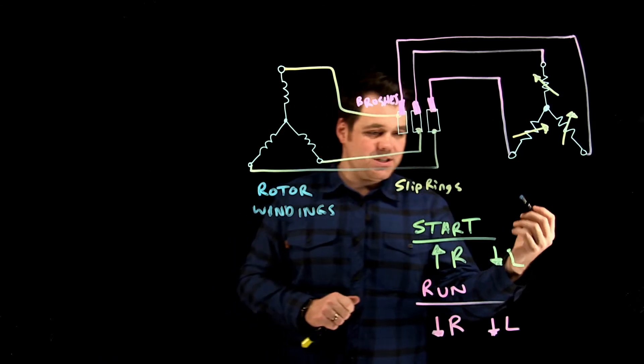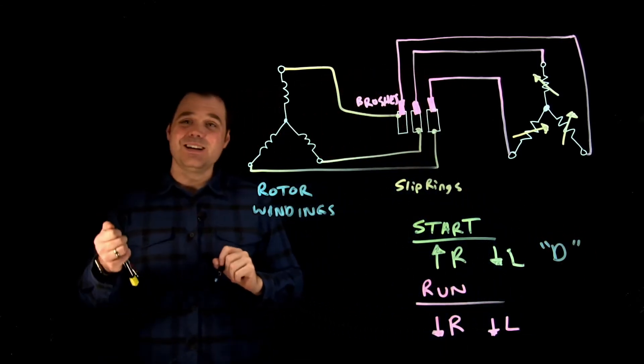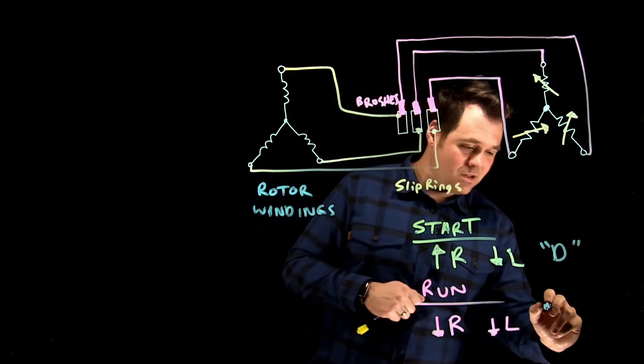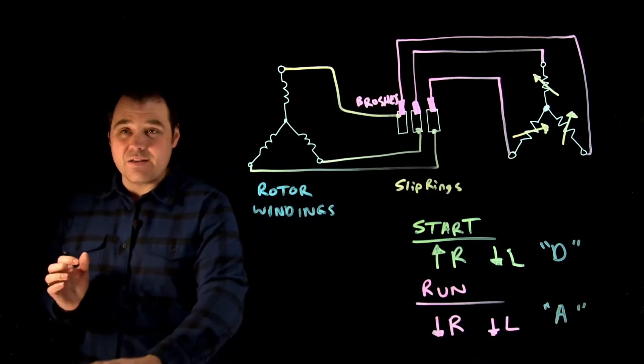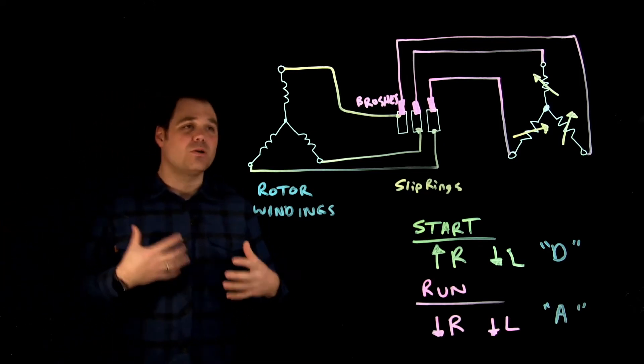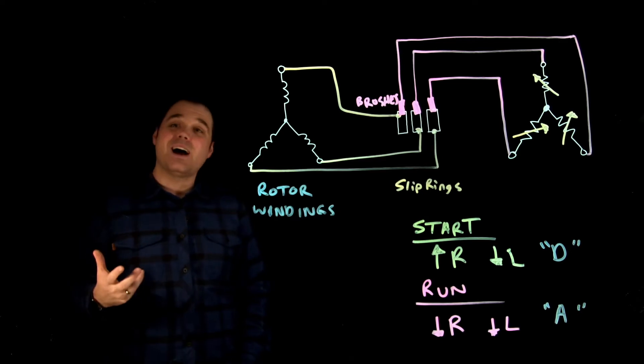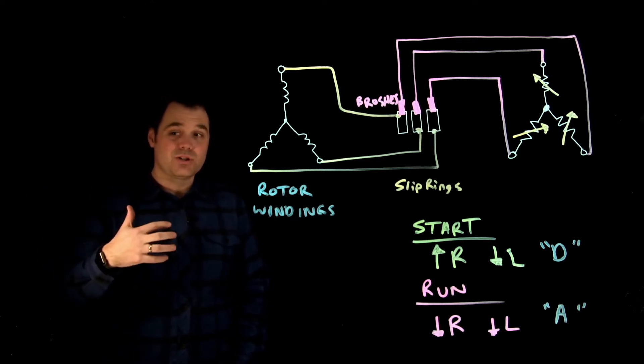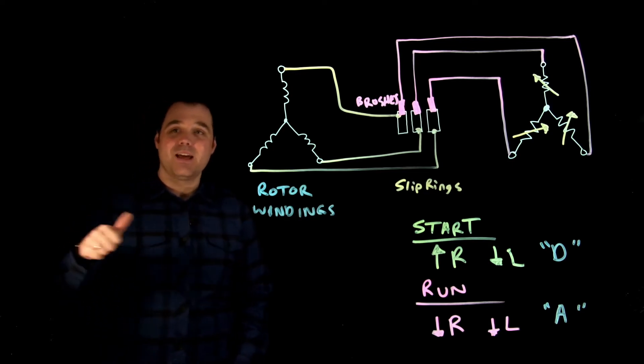So now, as it's running with a low resistance, it runs as a very efficient motor. So we say it starts like a D NEMA rotor design D, and we say it runs like an A, just because it's very efficient. Now, that's awesome. So I can get the best out of both worlds from this motor. That's my advantages of this motor, really high starting torque, low starting current. I really like that starts like a D runs like an A. That's awesome.